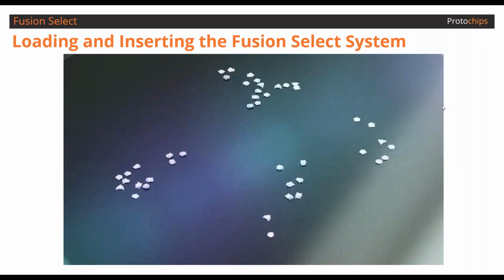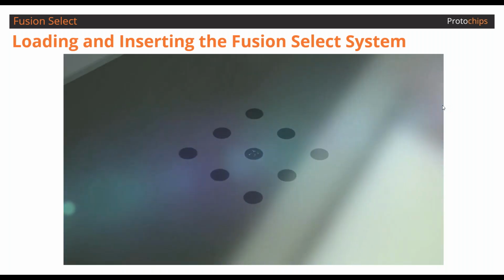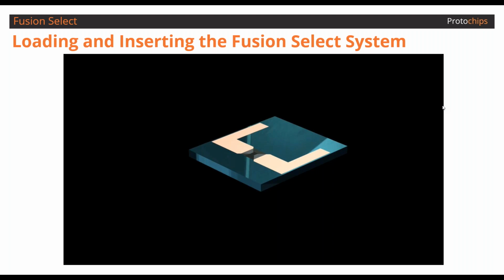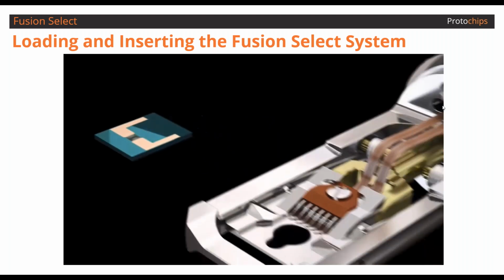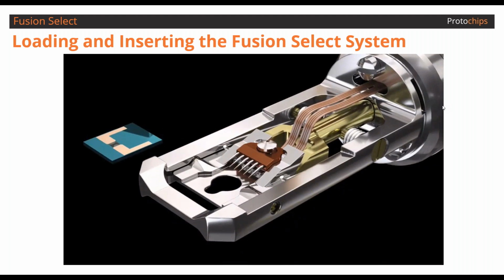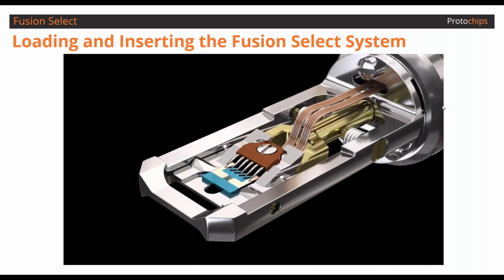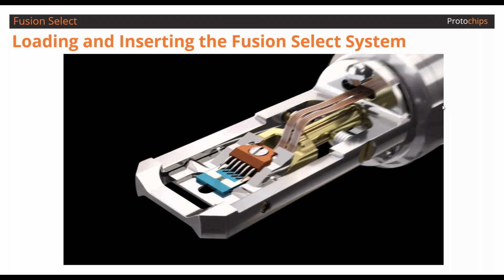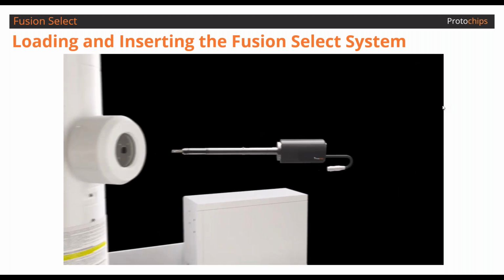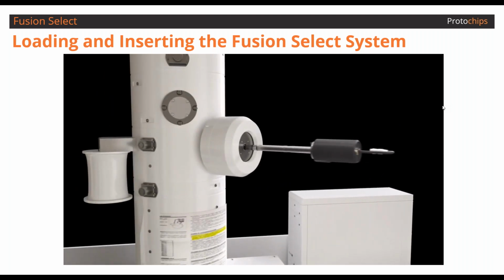So what does the full system look like? If we take the example of those white nanoparticles, they're placed at the center of the heater, in black here on this chip, and then you have electrodes running on the chip in order to reach contact pads. Those contact pads in yellow are connected with the probe as the chip is loaded, and the flex tracks bring the signal to the back of the holder. And this is where selecting the chip is going to select the function of your experiment. So now you can insert the holder inside the column, and you're ready for observation.